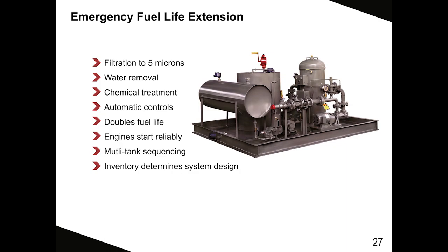And so Ed, looking at this large filtration unit here, you have a horizontal tank, and you've got this vertical tank with a hand pump, and then to the right of that, another cylindrical tank. Well, the cylindrical tank is where your filter cartridges are, with the high pressure lid, the ASME lid on it there. The tank closest to us is a biocide tank, the horizontal tank, for injecting a biocide to help stabilize your fuel or lengthen its usability.